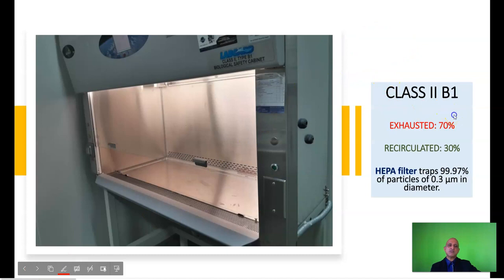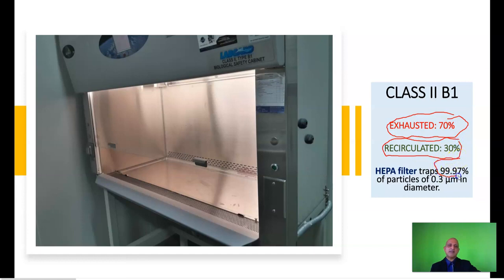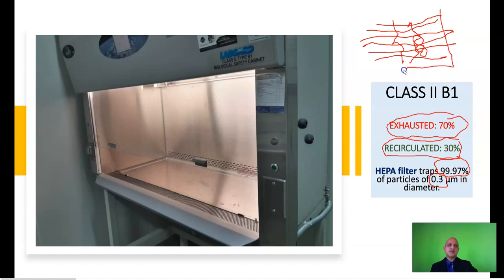The class 2 B1 exhausts 70% of the air and recirculates 30% of the air, and the HEPA filter in all cases traps 99.97% of the particles which are 0.3 micron in diameter. Now you will ask me, what happens to particles which are smaller than 0.3 micron? What you should note is that a HEPA filter consists of multiple layers of the filtering medium. So any particle which bypasses the first level will get trapped in the second level, and so forth. Secondly, the HEPA filter reduces the velocity of flow of air. When the velocity of flow of air is reduced, the particles tend to get trapped within the HEPA filter itself. So this is one of the considerations you need to take into account when you raise that question about the size of the virus or other pathogens and their likelihood of passing through the HEPA filter.